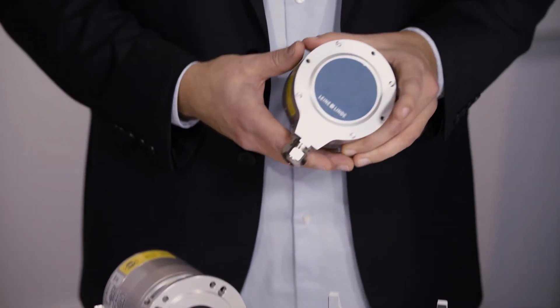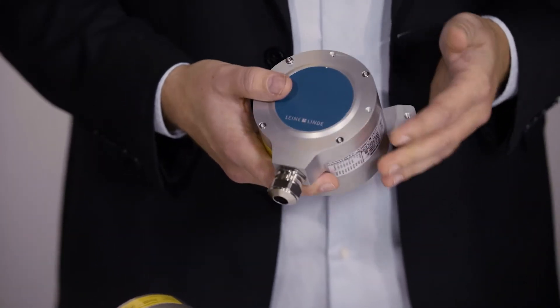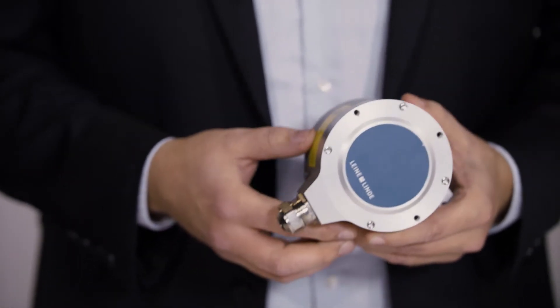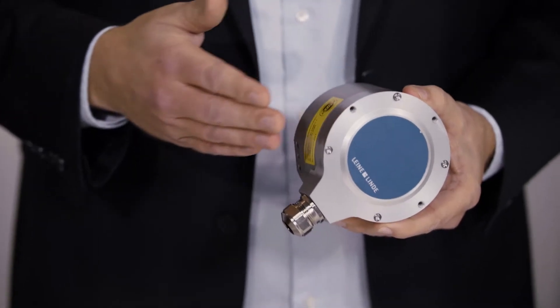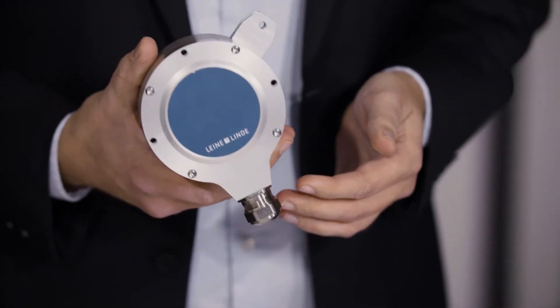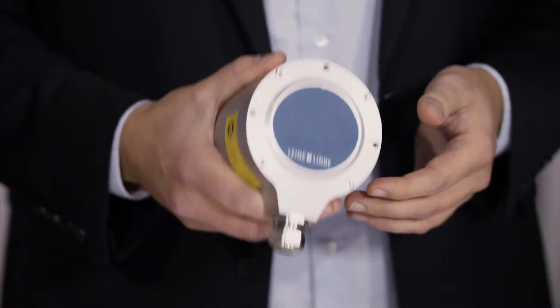This product here is actually a piece of magic. The FSI 800 is actually two encoders in one, which measures speed in a safe way. The measurements are compared and controlled all through the encoder, and it is certified for SIL 2 PLd, and it is built as a category 3 solution.